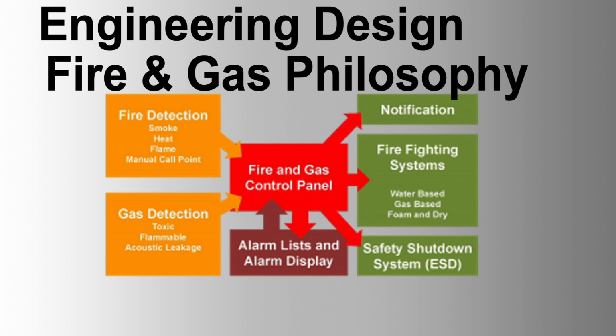Intersystem signals. From FGS to DCS, FGS functions should be independent of DCS, with non-safety signals transferred by soft links and all signals available via the process control network. From DCS to FGS, oil well cluster FGS nodes should connect to central processing facility FGS through a safety network. To IPS, when both FGS and IPS systems have a safety action on a final device, the combined trip signal should be carried by the IPS.